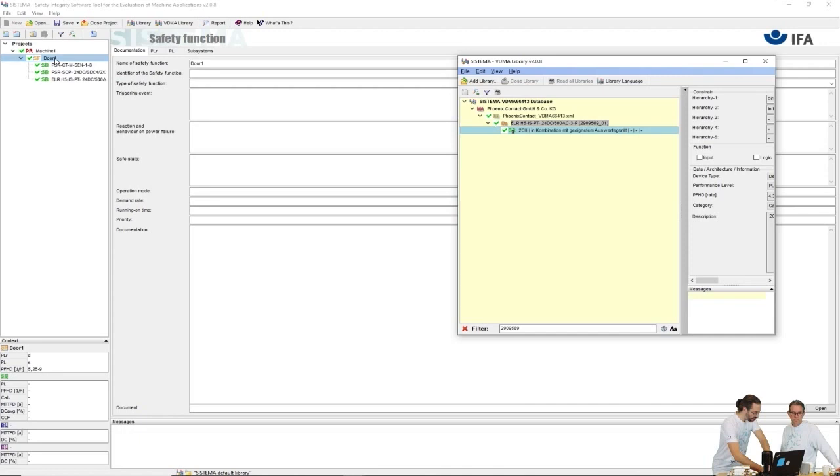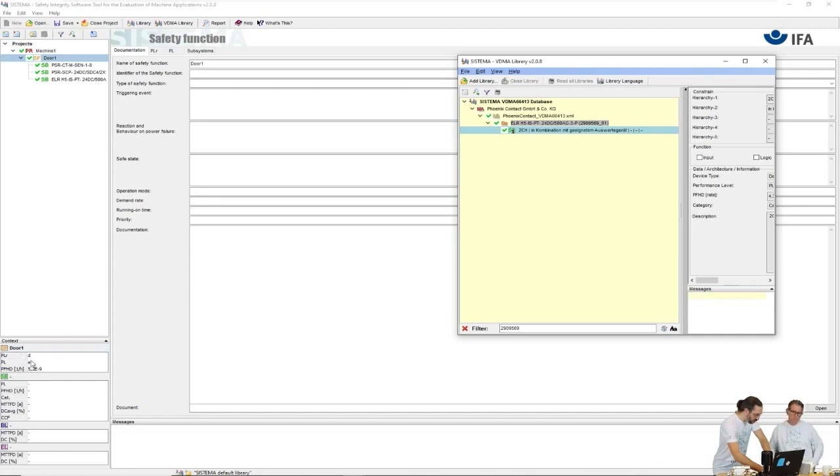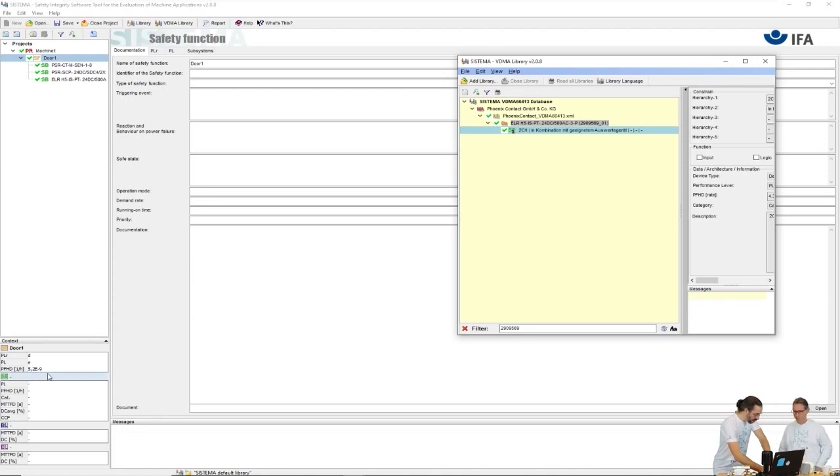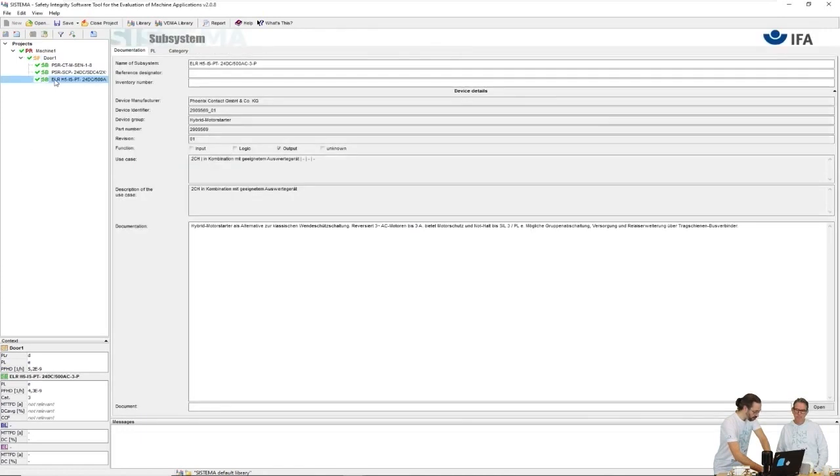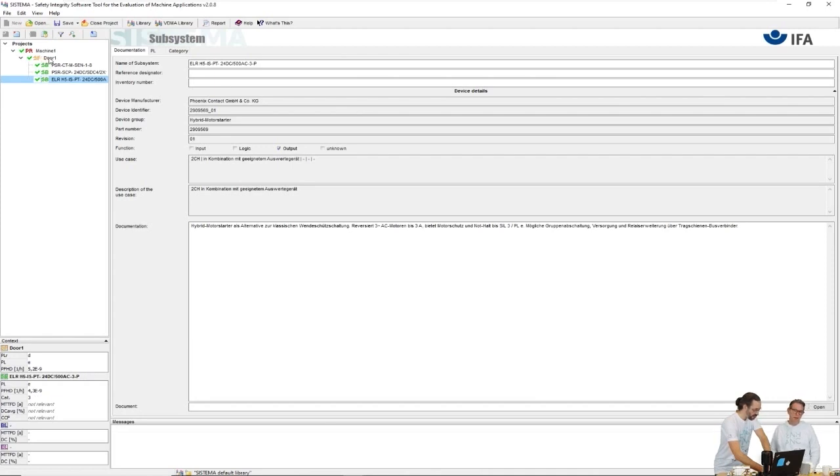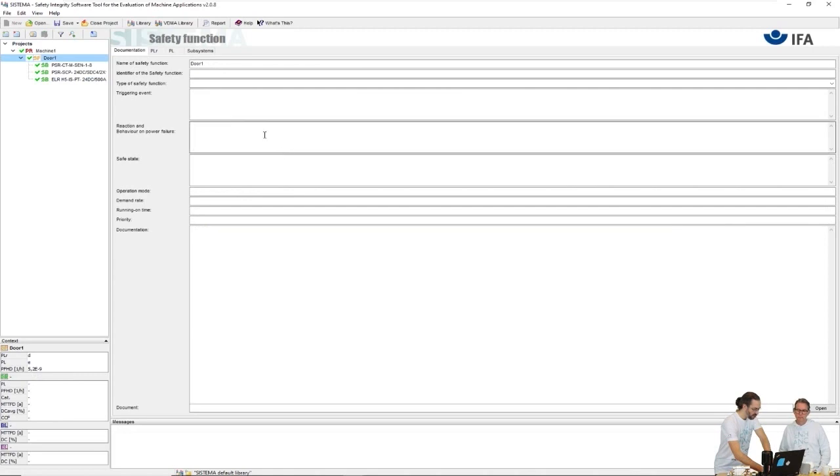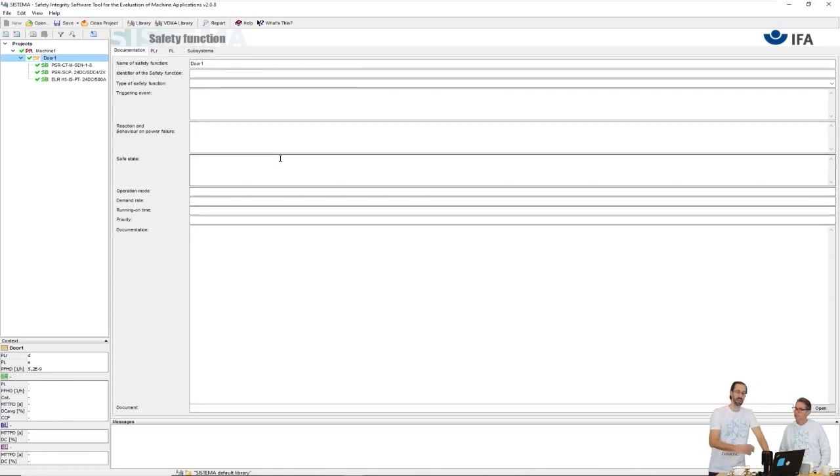Excellent, there we have the three products. We can now see on the safety function level PLD was required, we reach PLE in fact. Here we have the sum of the PFHd for the function. We can also check by marking different subsystems and see what's the individual data for them. As mentioned, for the report enter as much data as possible here to get it into the printed reports.